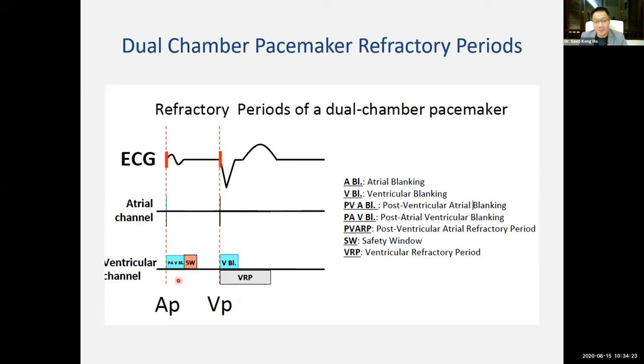Now, very important, because what happened in the atrium can determine what happens in the ventricle. So when the atrium has an event happen, either a pace or a sense event, there will be a post-atrial ventricular blanking. That means, for a moment, I don't want to see anything. And for the ventricular channel, there is this period here, a very peculiar period called the safety window. We shall talk about it more in a while, but for the time being, let's move on and talk about other things.